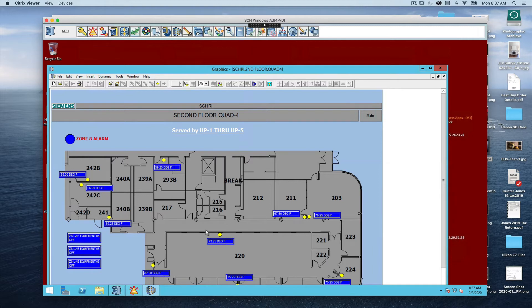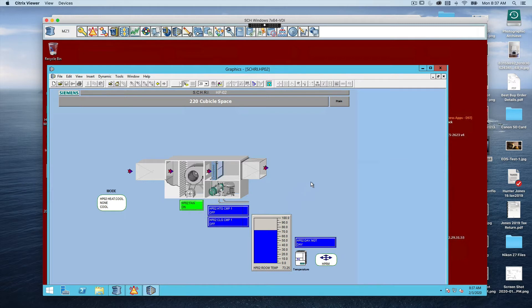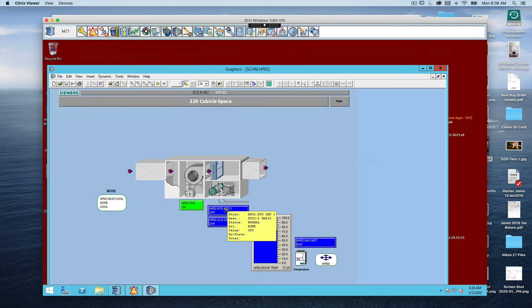What we do here is go back to heat pump number two — that's this control thermometer. We click and drag it off to the side lightly and it pulls up the control screen for that particular heat pump. You can see a graphic for the heat pump and its various components. The fan is on, the heating compressor is off, the cooling compressor is off, and here's the thermometer control — the temperature in the room is 73.25 degrees. We're going to take the heating compressor controller function and drag it up to the Report Viewer, which will open what they call a DOS report — a basic text report of the condition of this heat pump.